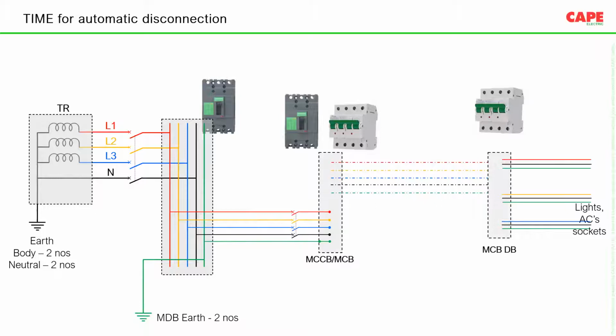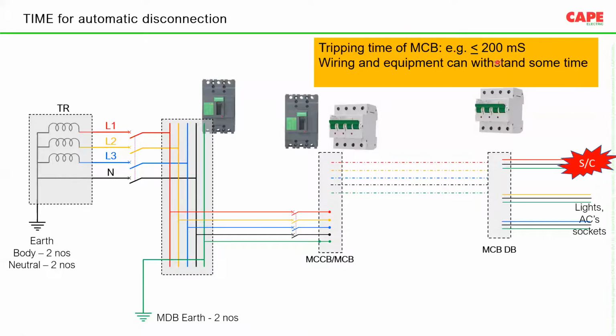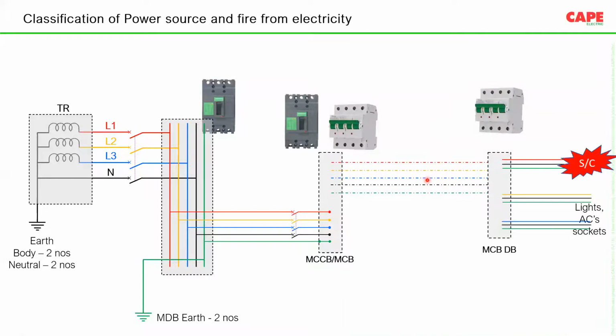This is not correct, because most of these hospitals have an overcurrent protective device. What is the purpose of installing an overcurrent protective device? In case of overload, this device should trip, and if this device is not tripping, of course, then there will be a problem. The tripping time in case of a fault of negligible impedance is less than 200 milliseconds. In case of a TT network, I have put TT network because most of the hospitals are TT. Wiring and equipment can withstand up to this 200 milliseconds. Actually, not 200 milliseconds, up to 3 seconds it can withstand. But the problem is most of the time the MCBs are not tripping because the MCB's tripping time is not tested. As I said, we don't know the situation.